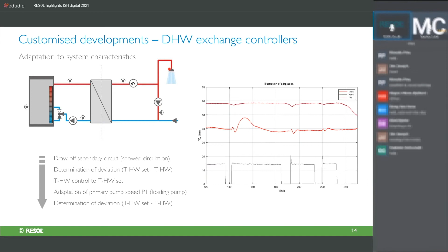The control system learns from how the system behaves and then adapts the control behavior to this. And in comparison to the first time, the fluctuation is also much smaller in the second and in the third time here. And also, to this point, the temperature is measured directly behind the heat exchanger at this point here, so that after the piping we have here, the temperature fluctuation is almost gone and no longer noticeable.